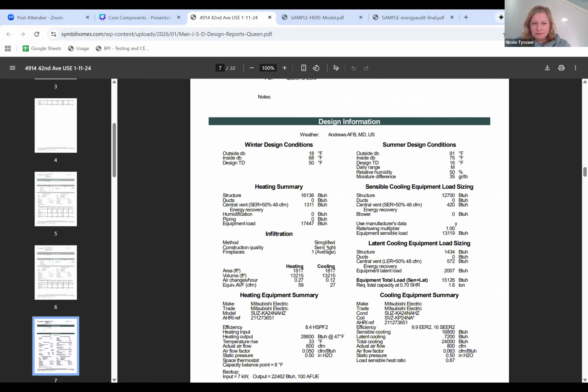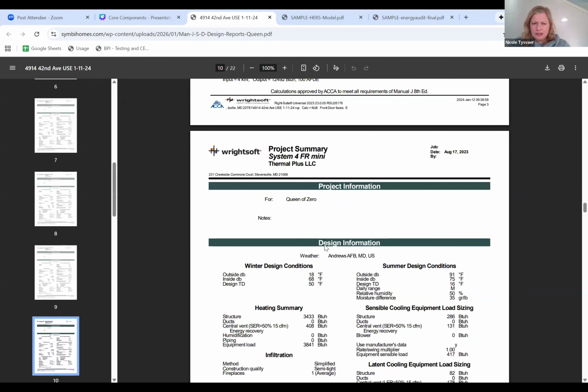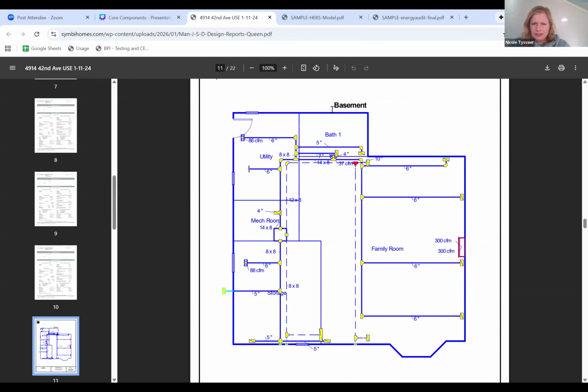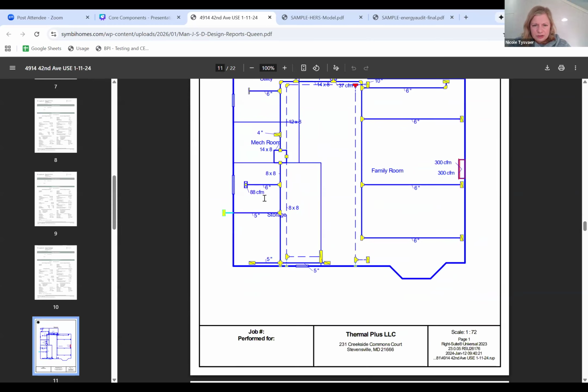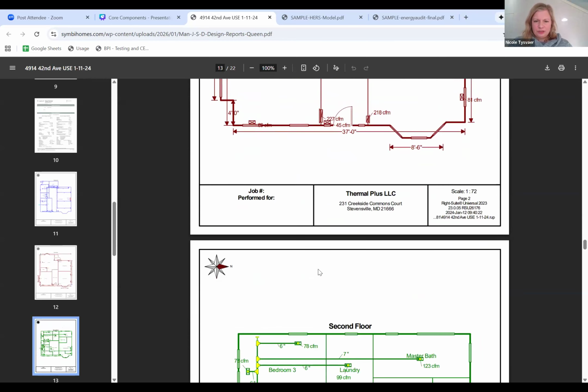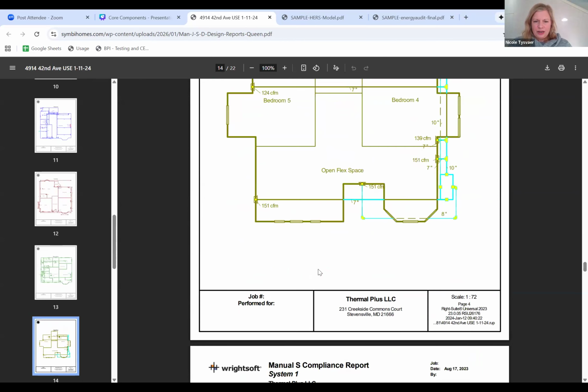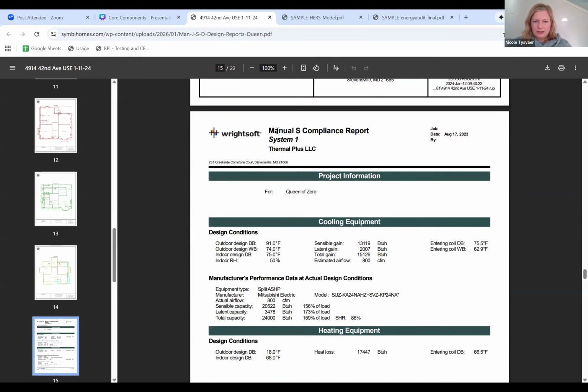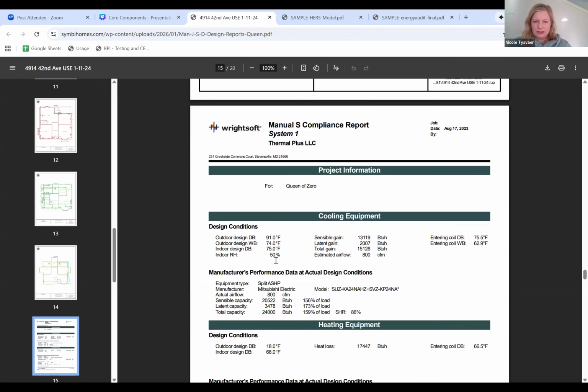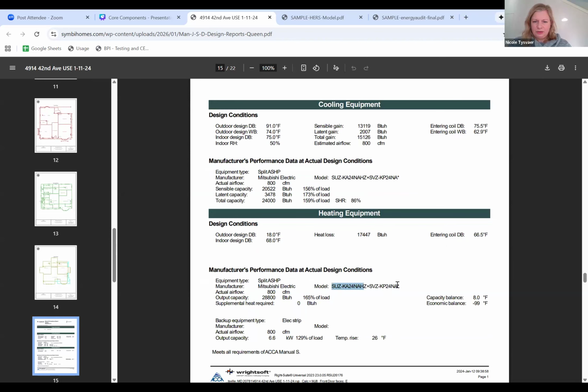After that you get into the actual duct design, the Manual D. It shows the layout of each floor and where the duct runs are going, and the CFMs per register, first floor, second floor. Then you get into the Manual S, which is the actual specifications of the piece of equipment, the model number, and those sorts of things.